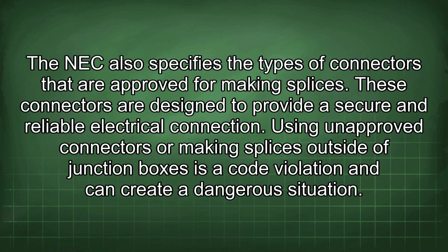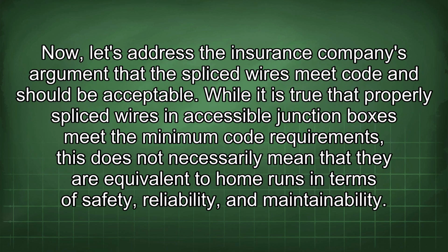The NEC also specifies the types of connectors that are approved for making splices. These connectors are designed to provide a secure and reliable electrical connection. Using unapproved connectors or making splices outside of junction boxes is a code violation and can create a dangerous situation. Now, let's address the insurance company's argument that the spliced wires meet code and should be acceptable. While it is true that properly spliced wires in accessible junction boxes meet the minimum code requirements, this does not necessarily mean that they are equivalent to home runs in terms of safety, reliability, and maintainability.